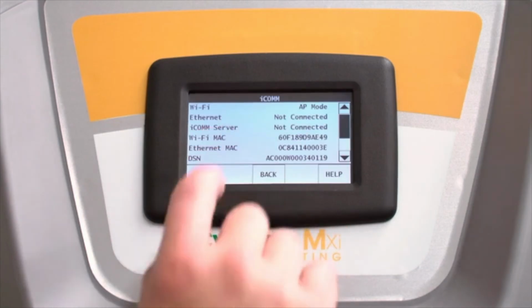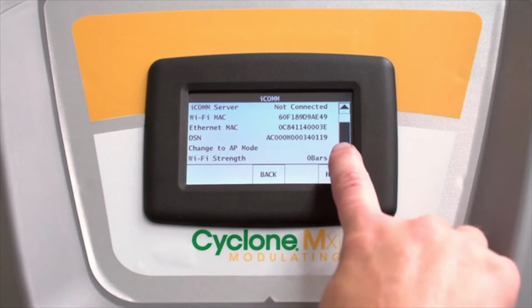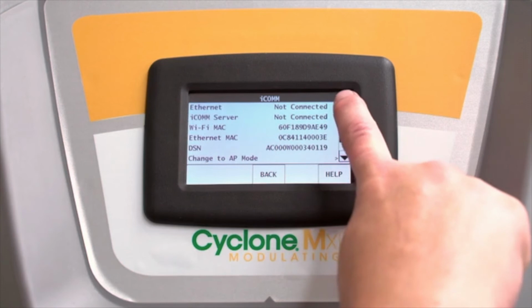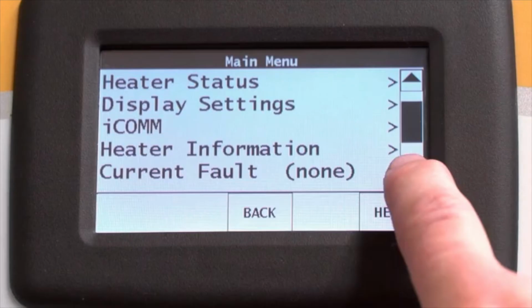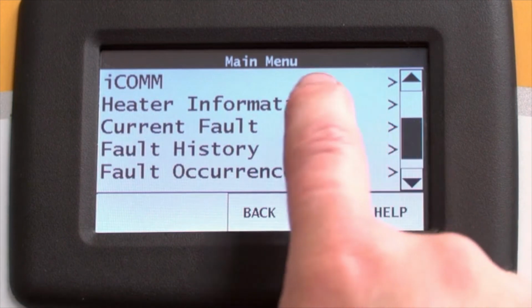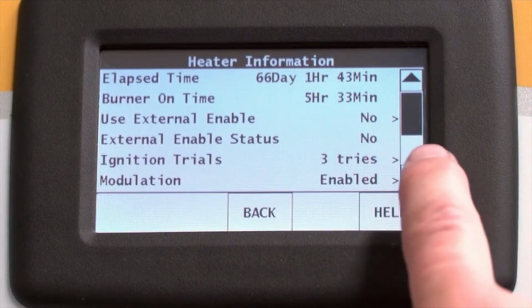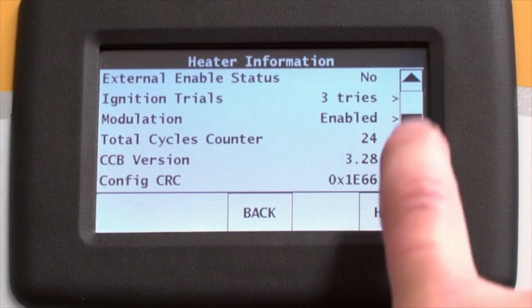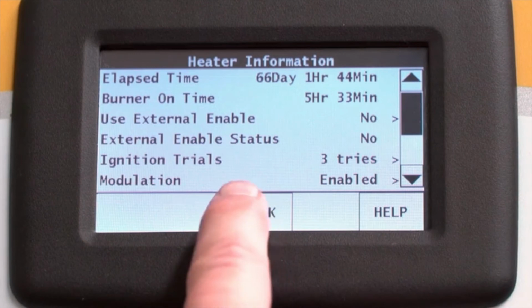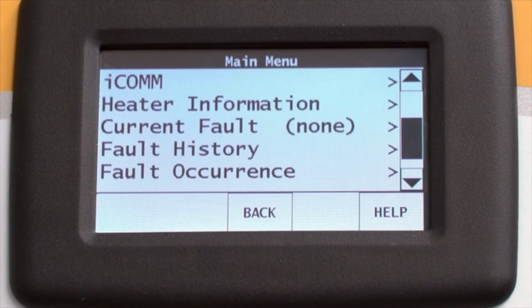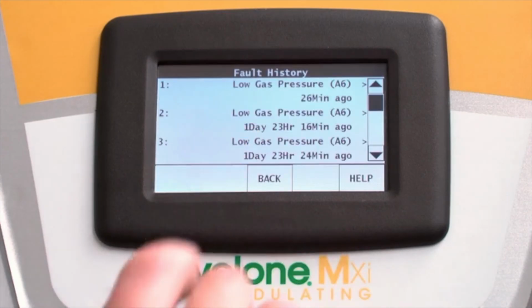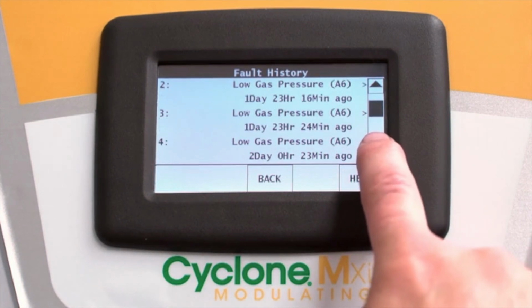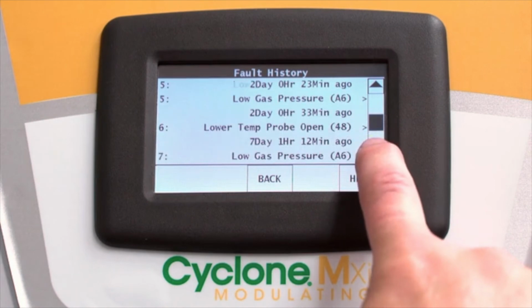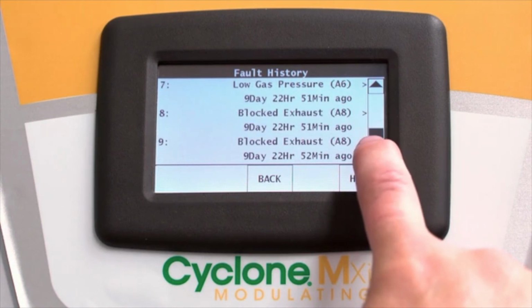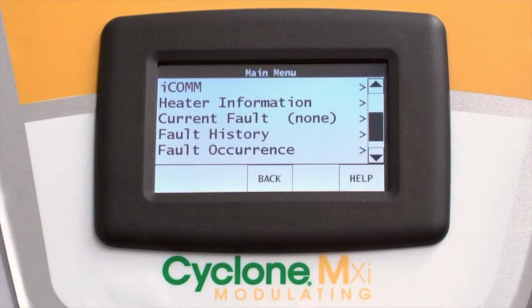The Cyclone MXI is compatible with the iCOMM connectivity service. The display will show you if the water heater is connected to the iCOMM service via Wi-Fi or Ethernet. Heater information shows the details of the operating life cycle of the Cyclone. You can check the amount of time the burner has been operating, the configuration, and the total cycle count since the water heater was installed. Current fault will tell you if there's an existing problem, and it provides diagnostic and repair information. Fault history provides visibility into the water heater's historical operations and can reveal common trends that may be causing improper operation. This is a valuable diagnostic tool for service technicians that helps them find and fix problems quickly.